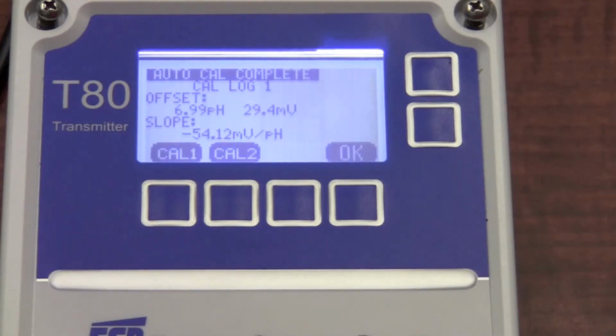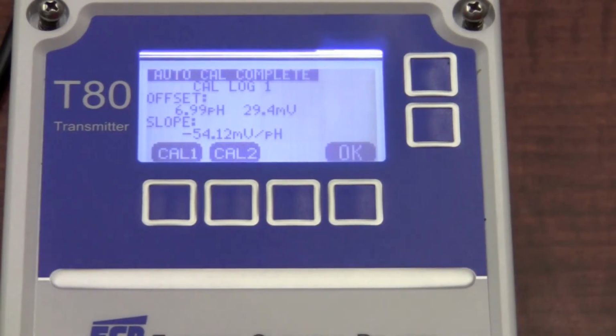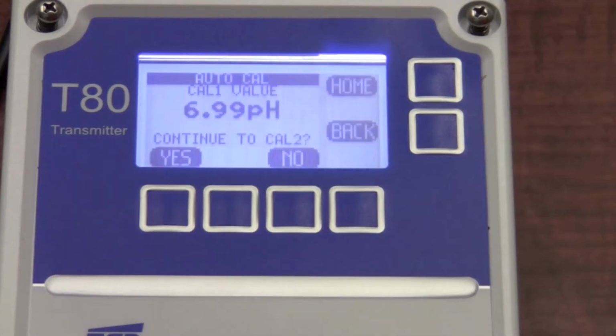The screen does give me an approximate slope as well. As you can see, it's minus 54.12 millivolts. 7 pH should always show you approximately 0 millivolts. You would get an offset with degradation over time of the reference half cell that's exposed to the process. In our particular case, we see that we still have an acceptable slope of 54.12. That's acceptable up to approximately 50 millivolts.